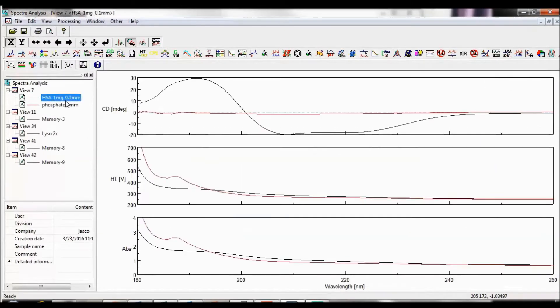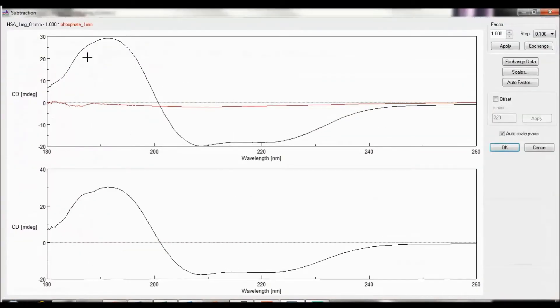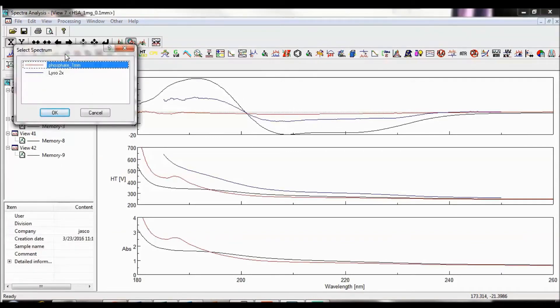Under the Operations submenu in the Processing tab, Arithmetic performs arithmetic operations between spectra or between a spectrum and a constant. To perform arithmetic operations between two spectra, more than one spectrum must be in the active view. However, CD typically only requires a subtraction operation to remove the buffer spectrum from a sample CD spectrum. The Processing tab has a separate subtraction function which can also be selected by clicking the subtraction icon in the Processing menu bar. To subtract a buffer spectrum from a sample spectrum, overlay the buffer spectrum in the sample spectrum's view. Select the sample spectrum and either choose the subtraction icon or go to Processing, Subtraction. If more than two spectra are in the active view, you'll be prompted to select which spectrum to subtract from the highlighted spectrum. In this case, we will be subtracting the buffer spectrum from our sample spectrum.